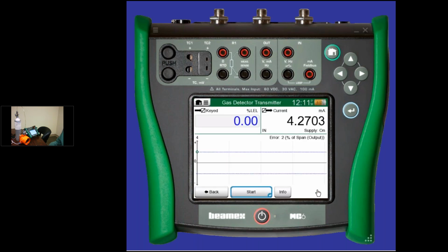But this test is set up for measuring the milliamps, and actually it's off here. It's barely passing. It's right at 2% of span, and there's my pass-fail. So here I am at ambient conditions, and I'm getting 4.27 milliamps. So let's go ahead and start this test.